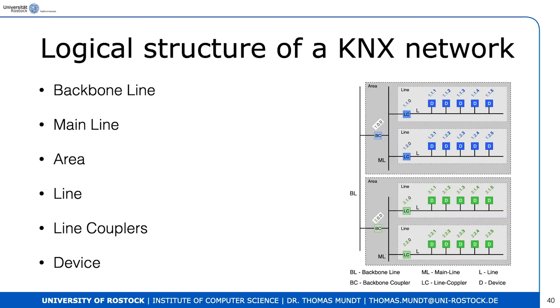The logical structure of a KNX network: there are backbone lines that interconnect larger parts — areas — of the network. An area is formed by, for example, all floors. In our building with four floors, we have four areas. The backbone line is an actual cable running between floor levels. These addresses reflect the structure — an area is encoded in the first part of the device address.